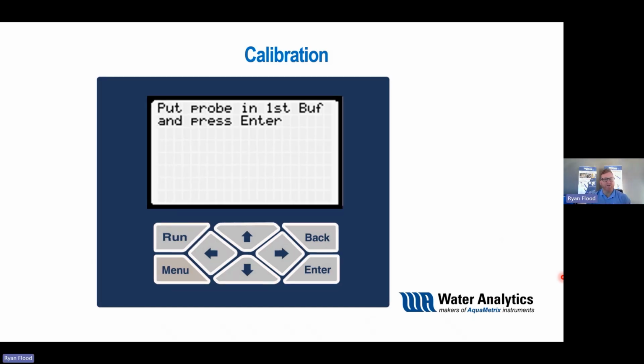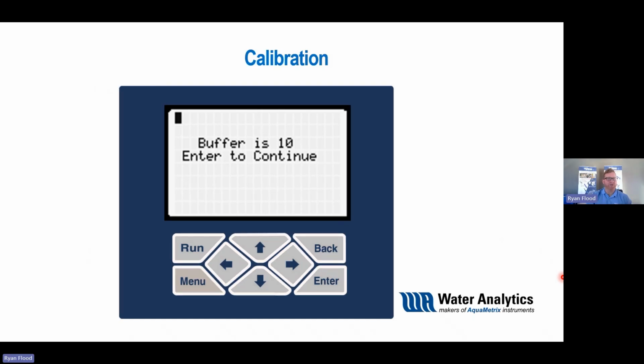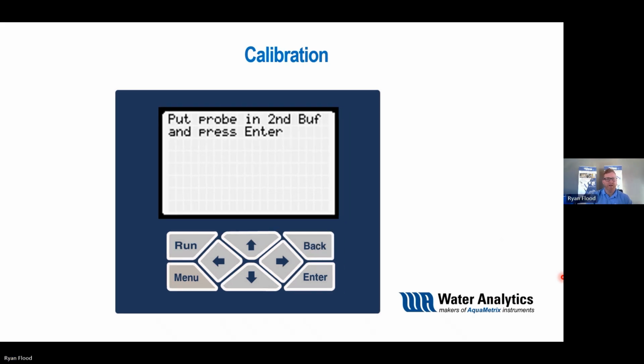So then you're going to move into, let's say we've chosen the auto. You're going to put it in the first buffer solution. Once it's in there, you're going to go ahead and hit enter. It's going to detect what that is. Again, in this instance, it's detecting that it's 10. If it is in 10, you're going to hit enter. Again, like I said, if it's not, that's a good indication you should be performing some maintenance. Then you're going to go ahead and put in the second buffer solution. It walks you right through this, which is great.